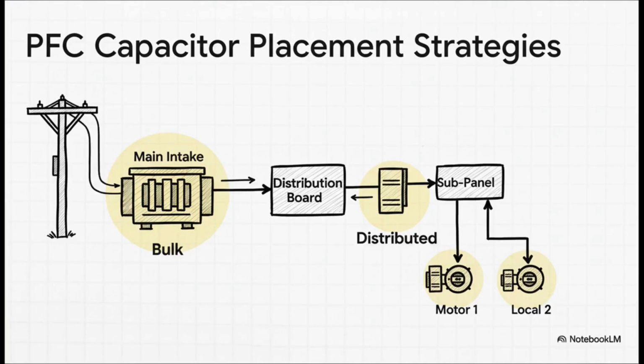As a designer, you've basically got three main strategies. You could do local correction, putting a capacitor right at each individual motor. That's super effective for reducing current all through your wiring, but that can get pretty expensive. Or you could do distributed correction at a subpanel. But honestly, the most common approach by far is bulk correction, installing one large capacitor bank right at the main intake. This fixes the power factor for the whole site, which is what the utility company really cares about.